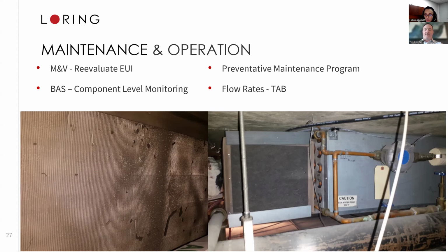However, in a refrigerant system, if you're not getting the expected airflow across the coil, you start developing ice buildup, and then you can actually develop a dam of ice in your HVAC unit, and it will shut the unit off, and then you'll have to come investigate why. And oftentimes it's because of filtration problems like this. Next slide.